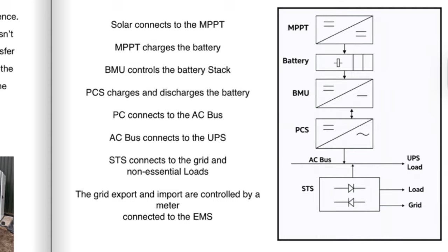But how does it work? On the right-hand side, I'm showing you how the actual units work. The solar connects to the MPPT, the maximum power point tracker. It's basically a DC to DC converter, and the solar panels connect to that. They then charge the batteries, and it's actually charged by the BMU. The drawing doesn't quite show it, but the energy will go through the BMU, the battery management unit. It will charge the batteries, and then the batteries will eventually discharge through the BMU into the PCS. The PCS is a bi-directional unit, and the PCS connects to the AC bus.